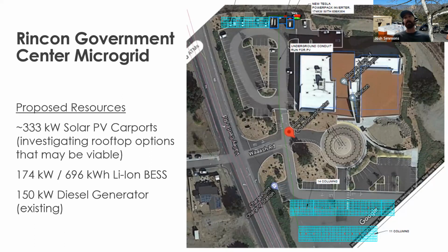It's actually kind of sitting there, and to a certain degree, it can be costly to just continue to maintain and operate it. This type of system, a renewable energy microgrid system, is going to provide value beyond just during the outage. Energy costs are increasing, likely across the country. They're very high, and with all the microgrids that I'm working on in San Diego County, we've seen spikes of 20-ish% over the past 2 years in electricity costs. So having solar and energy storage means you can displace the grid usage and grid costs. The battery helps you reduce the demand charges that you're otherwise experiencing.